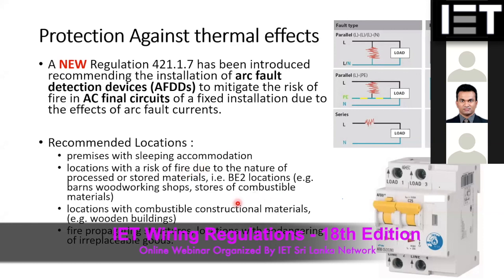And if there is a fire risk, especially the BE2 category. BE2 is external influences, risk of external influences. Those are categorized as BE1, BE2, BE3, BE4, like that. BE2 means where there is a risk of fire, and if you have a location with a risk of fire, then you have to go with arc fault detection.